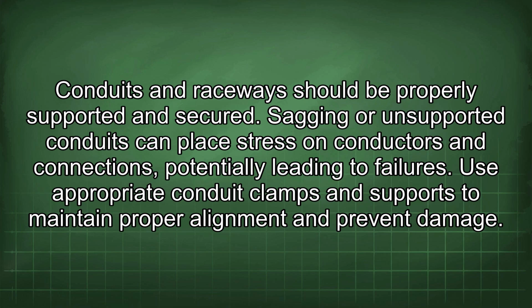Conduits and raceways should be properly supported and secured. Sagging or unsupported conduits can place stress on conductors and connections, potentially leading to failures. Use appropriate conduit clamps and supports to maintain proper alignment and prevent damage.